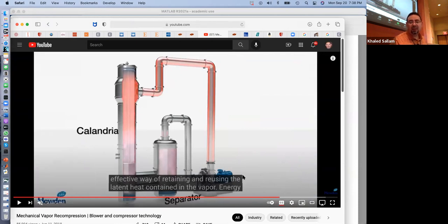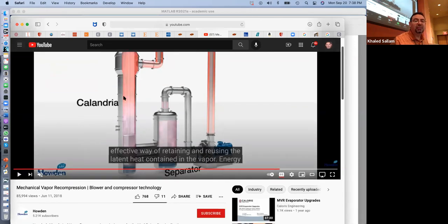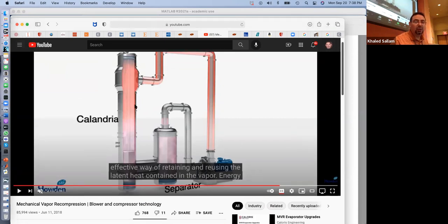So the compressor, also known as the vacuum pump, also known as the vapor compressor, takes that hot vapor and condenses it into liquid while doing what? While the water that comes from the top gets turned into vapor. So he's recovering the latent heat. The hot vapor becomes liquid while the water that's being sent into a film is basically being turned into vapor, right?